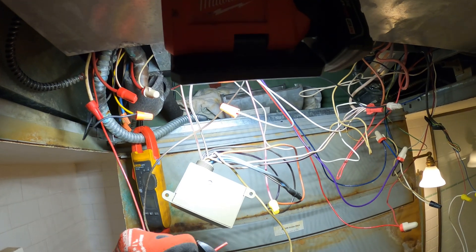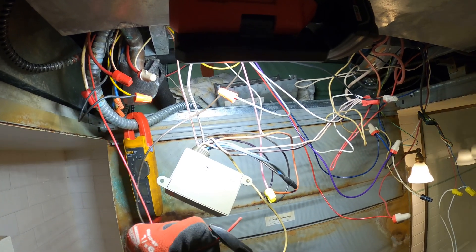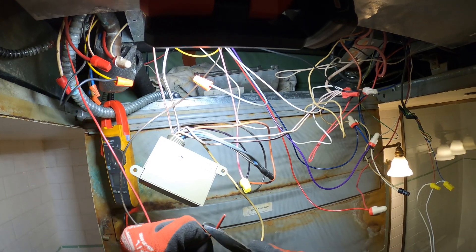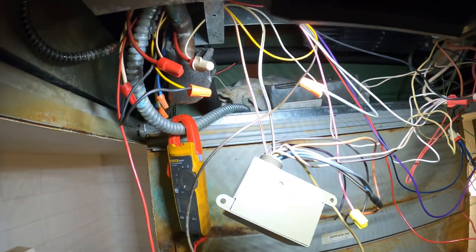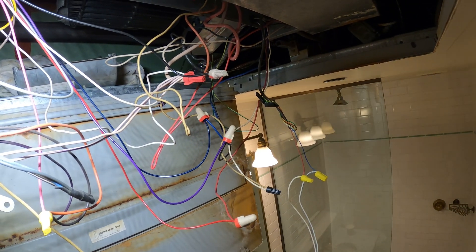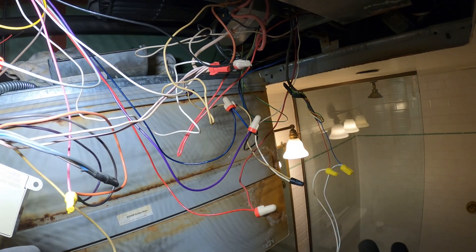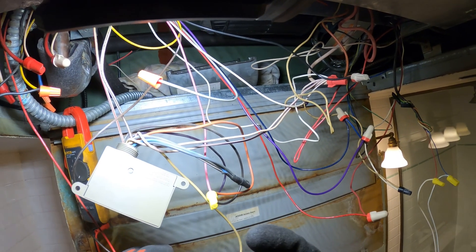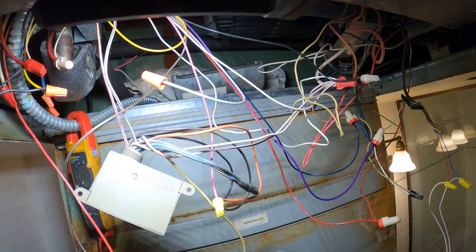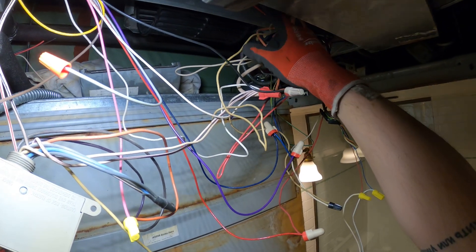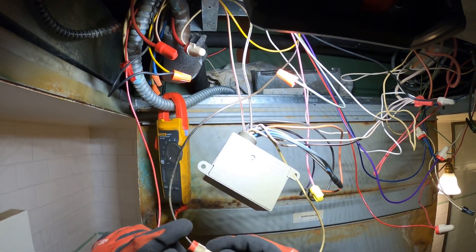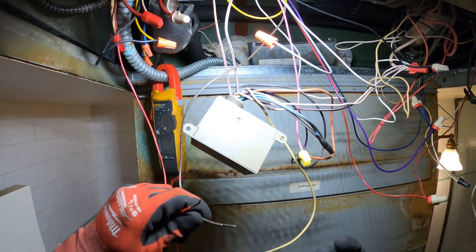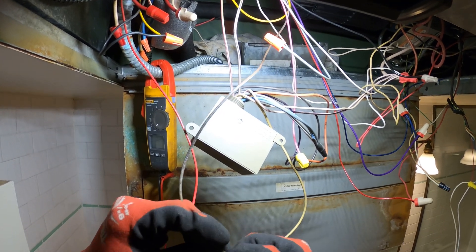So, now, what I want to do is, we call for cooling right now in this season. It's going to automatically open up. Go straight to that actuator. Open up the chilled water. Done. That works. Got the three fan speed. That works. Now, what we call for heating. It's going to just directly energize this heat relay. Because the boiler is not on. It's only a two pipe system. So, you can't have heating and cooling at the same time. It's one or the other. Right now, you're in cooling mode. So, the actuator is going to produce the chilled. It's going to open up the chilled water. That's how we get cooling. But as far as heating right now, we can just, as soon as that 120 volts comes out and set the thermostat, it's going to energize the coil on this relay and then send line voltage to the heat. And this is that wire right here, I believe. So. We're going to test it.